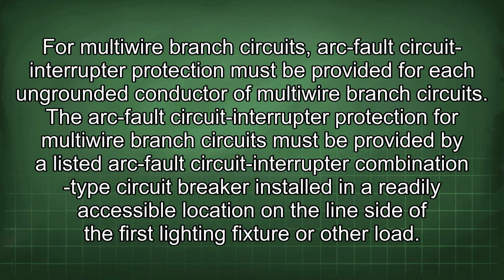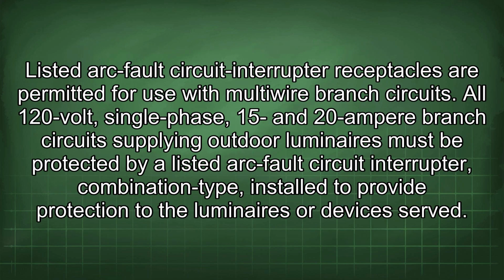For multi-wire branch circuits, arc fault circuit interrupter protection must be provided for each ungrounded conductor of multi-wire branch circuits. The protection must be provided by a listed arc fault circuit interrupter combination type circuit breaker installed in a readily accessible location on the line side of the first lighting fixture or other load. Listed arc fault circuit interrupter receptacles are permitted for use with multi-wire branch circuits.